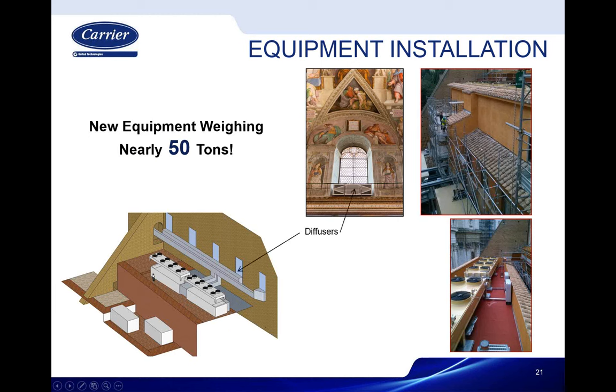So the diffusers are under each window, 4 supplies and 1 each return outboard, for a total of 6. The dry coolers - if we don't use the heat of compression coming out of the cooling side for reheat, we have to exhaust it to the atmosphere. We do use that, and if we do not have the reheat capability from the captured heat, there are electric heaters.